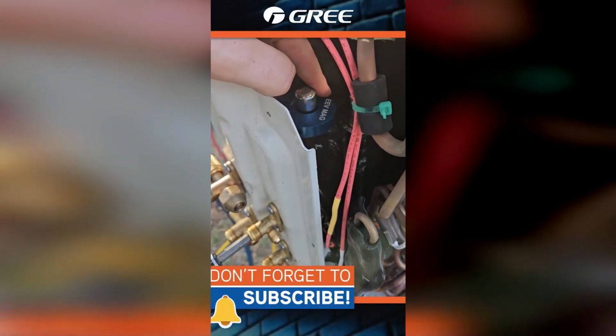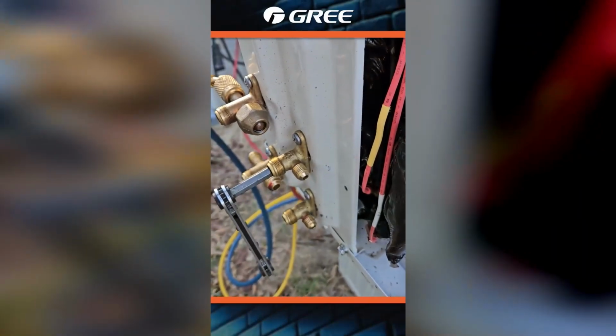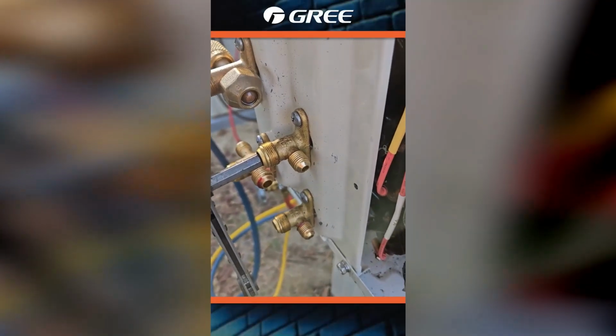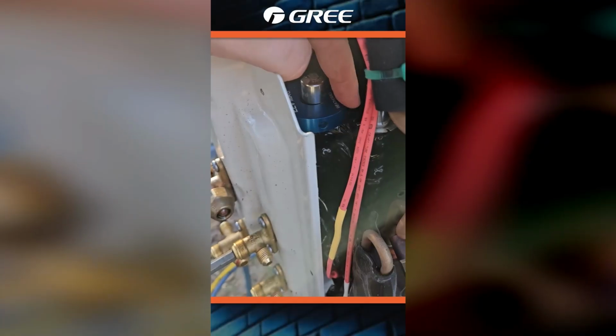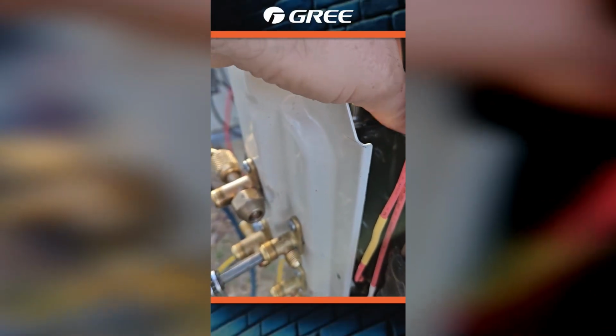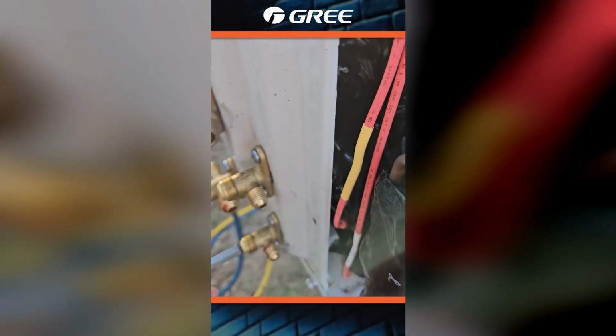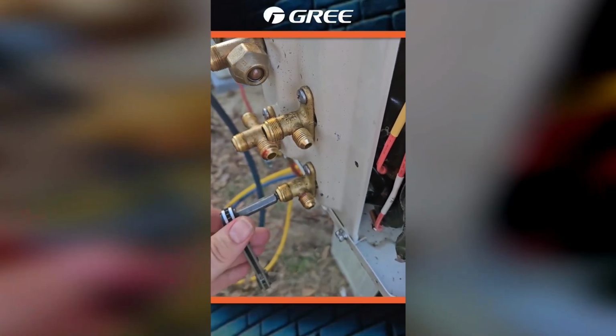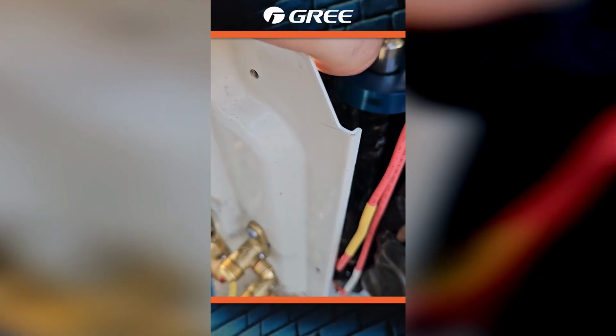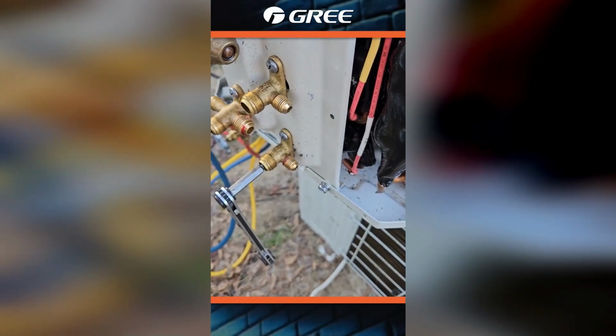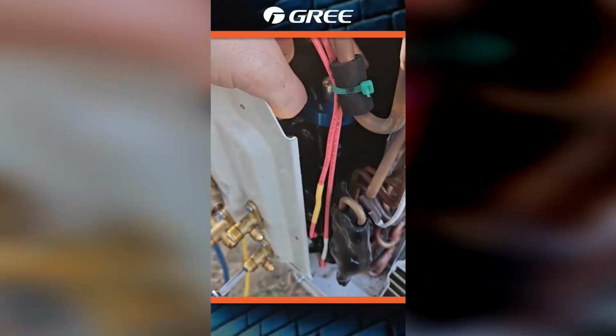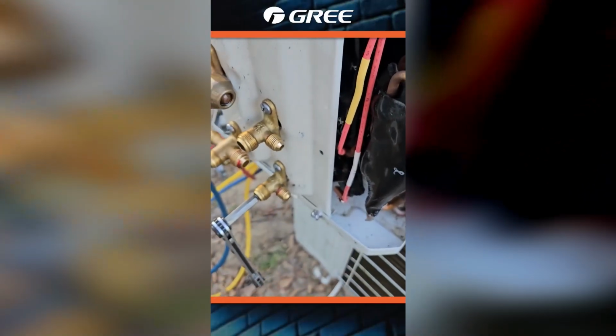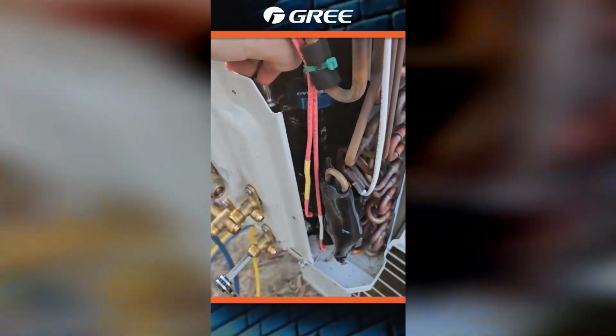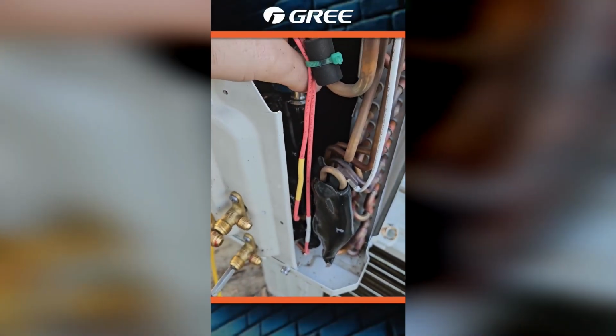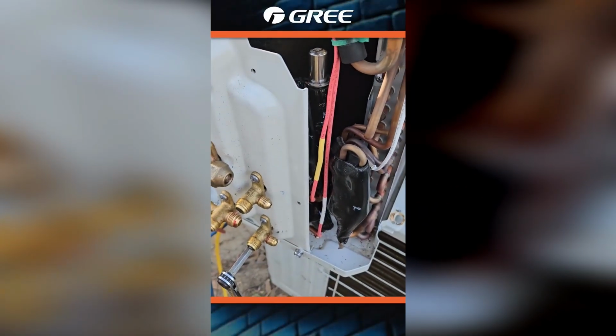So I decided to take the unit apart, use the EEV Mag, and adjust the EEV manually with the magnet to see if I get pressure out of either of these valves. You can hear the pressure coming out of this one as I turn this, and you can hear it stop as I turn it back closed. However, moving to this one, just make sure that my valve is open here. So it's all the way open, and spinning this should open and we get some pressure out of that A port, but it's not doing anything at all, spinning it either way. So I believe some of that Loctite that was used on the flares actually got into the EEV and has locked up the piston inside there. So, all right.